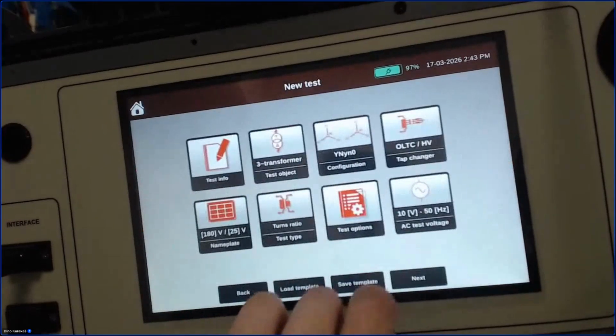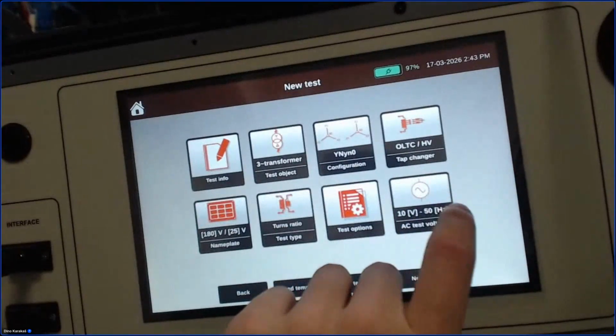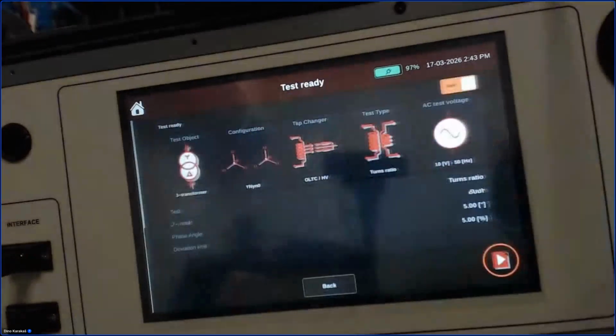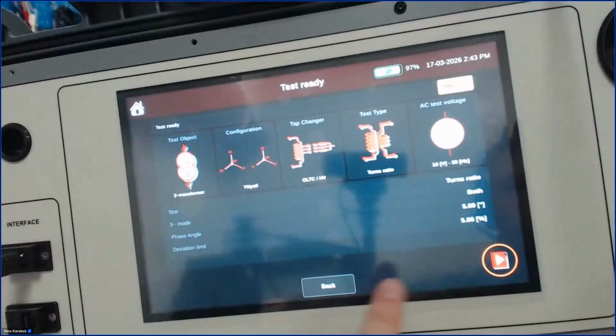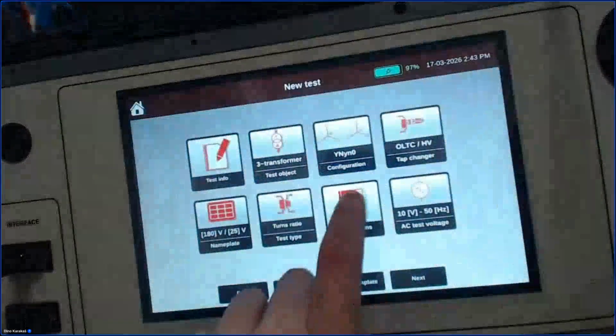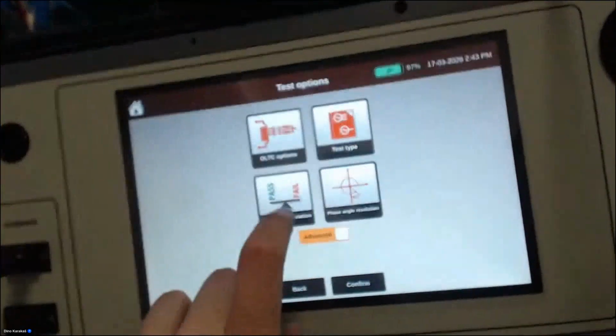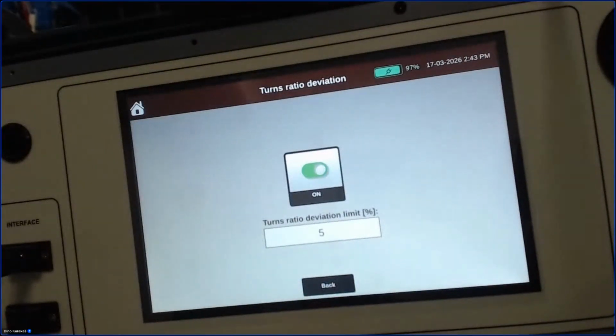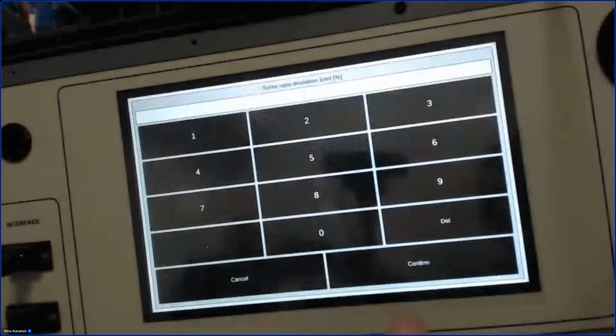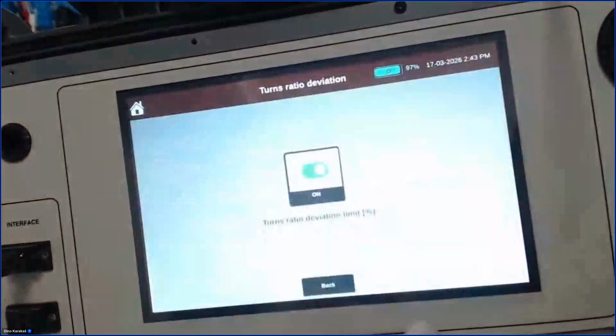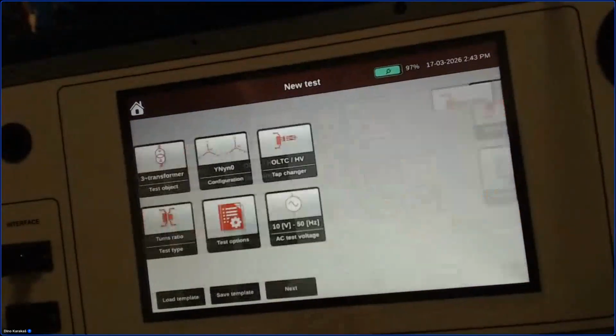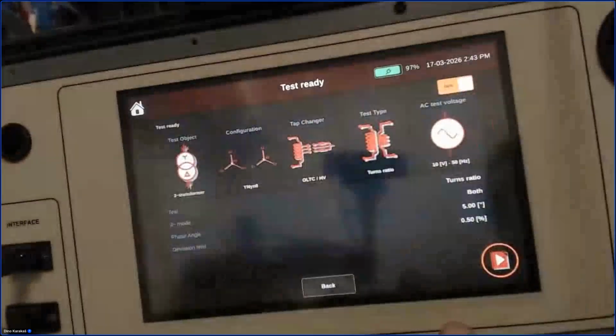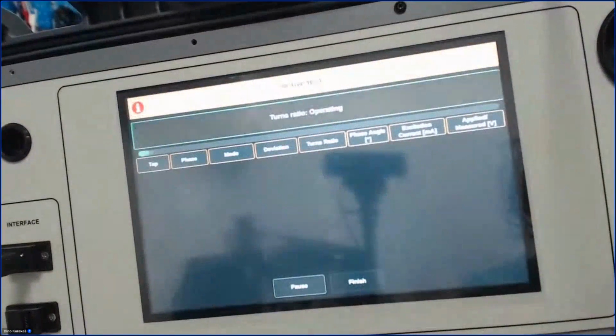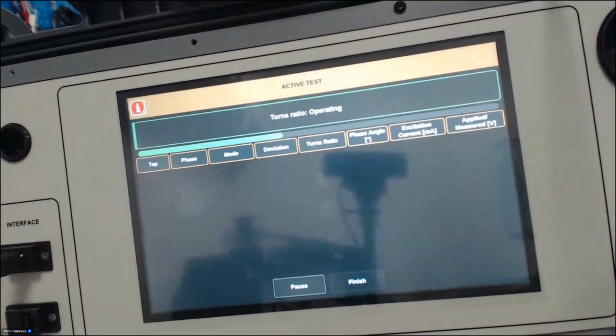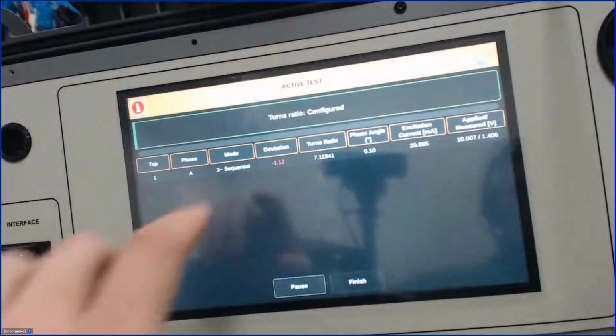It's okay. And we select the test voltage, which can be 10 volts in this case. We go next. We can double check. We forgot to put the deviation limit here. Pass-fail criteria. 5% is too much. The standard says 0.5. And since I have experience with this transformer, which is probably older than me, we can expect a huge deviation. And you will see that this value will turn red. You can see it here.